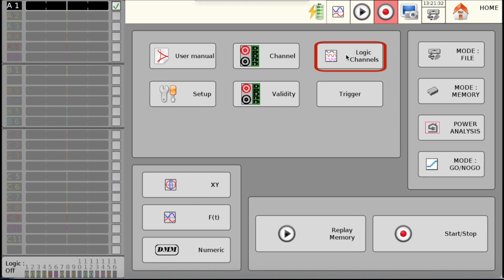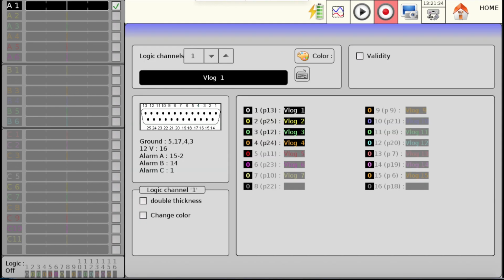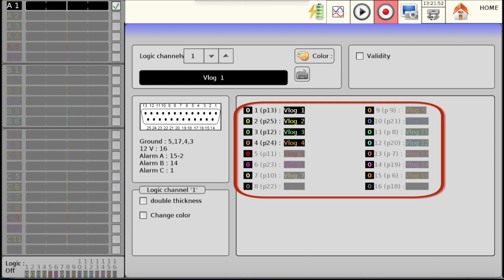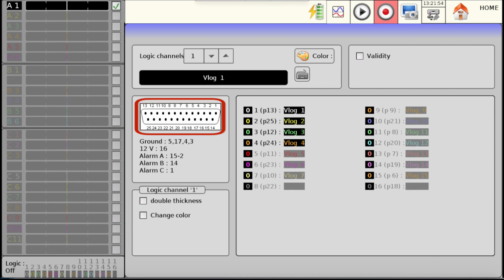The Logic Channels menu allows to access the parameters of the logic channels. The instrument is equipped with a sub-D25 connector to manage all logic signals. There are 3 alarm outputs: A to C, one 12-volt output for external power supply, and 16 logic inputs. A numbered diagram for your wiring is shown on this page.